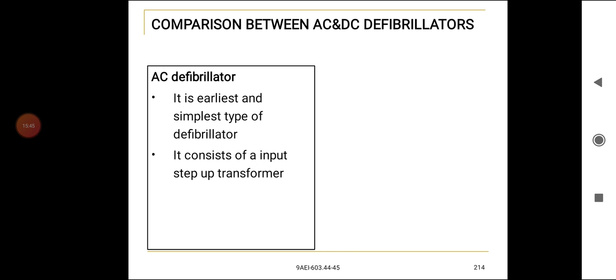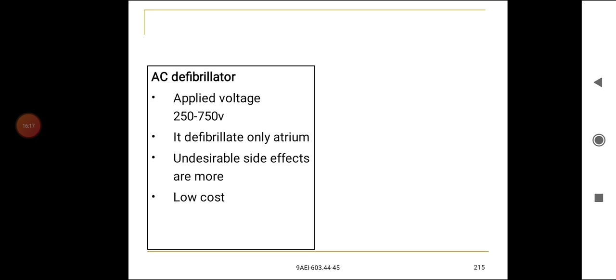The comparison between the AC and DC defibrillators. AC defibrillator is the earliest and simplest type of defibrillator. It consists of an input step-up transformer. Whereas the DC defibrillator has a larger circuit compared with the AC defibrillator. It consists of an input auto transformer and capacitor. AC defibrillator applied voltage is 250 to 750 volts. It defibrillates only the atria. Undesirable side effects are more, low cost. Whereas DC defibrillator applied voltage is 1000 to 8000 volts. It defibrillates ventricles also. Undesirable side effects are less, high cost.